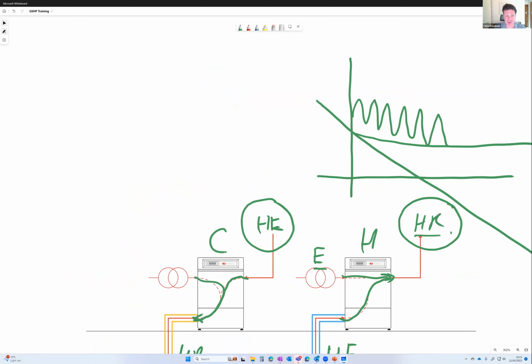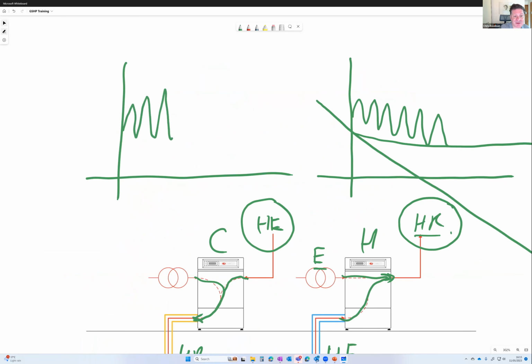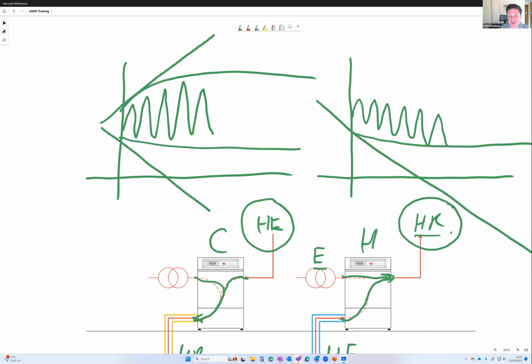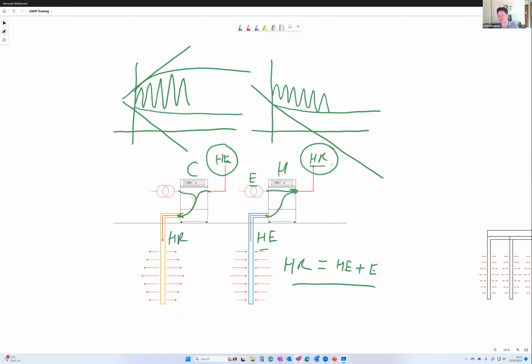If we've got a heating and cooling system, the graph goes both ways, and we'll get warmer in the summer, colder in the winter. Exactly the same, we don't want that to just get hotter and hotter and colder and colder. We want it to tend to a limit. So that's, in a nutshell, the process of closed loop design for ground source systems.